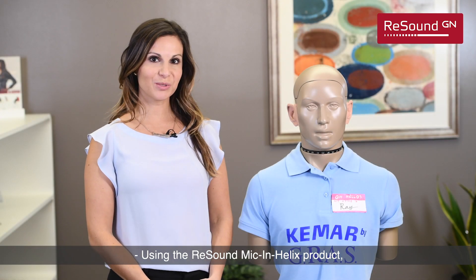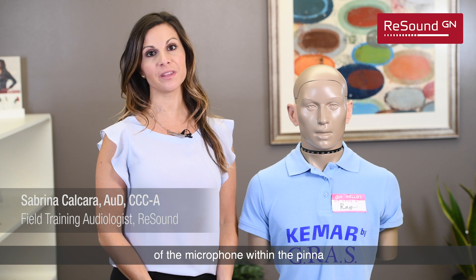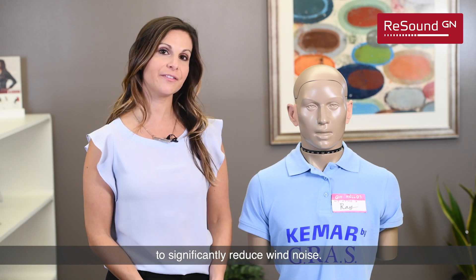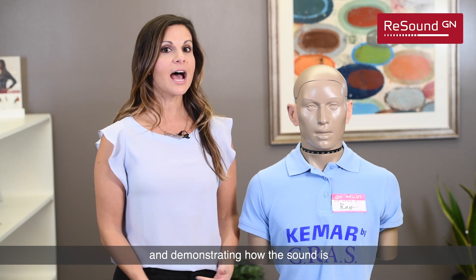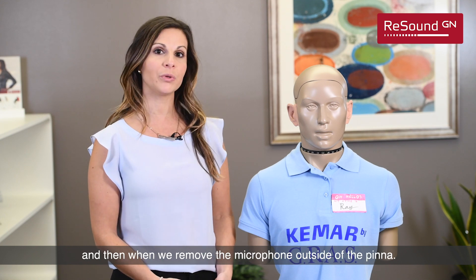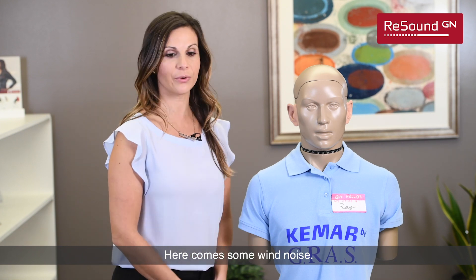Using the ReSound Mic-In-Helix product, I'm going to demonstrate how the placement of the microphone within the pinna allows the pinna to act as a natural barrier to significantly reduce wind noise. I'm going to do this by activating some wind noise and demonstrating how the sound is when the microphone is in the pinna and then when we remove the microphone outside of the pinna. So here comes some wind noise.